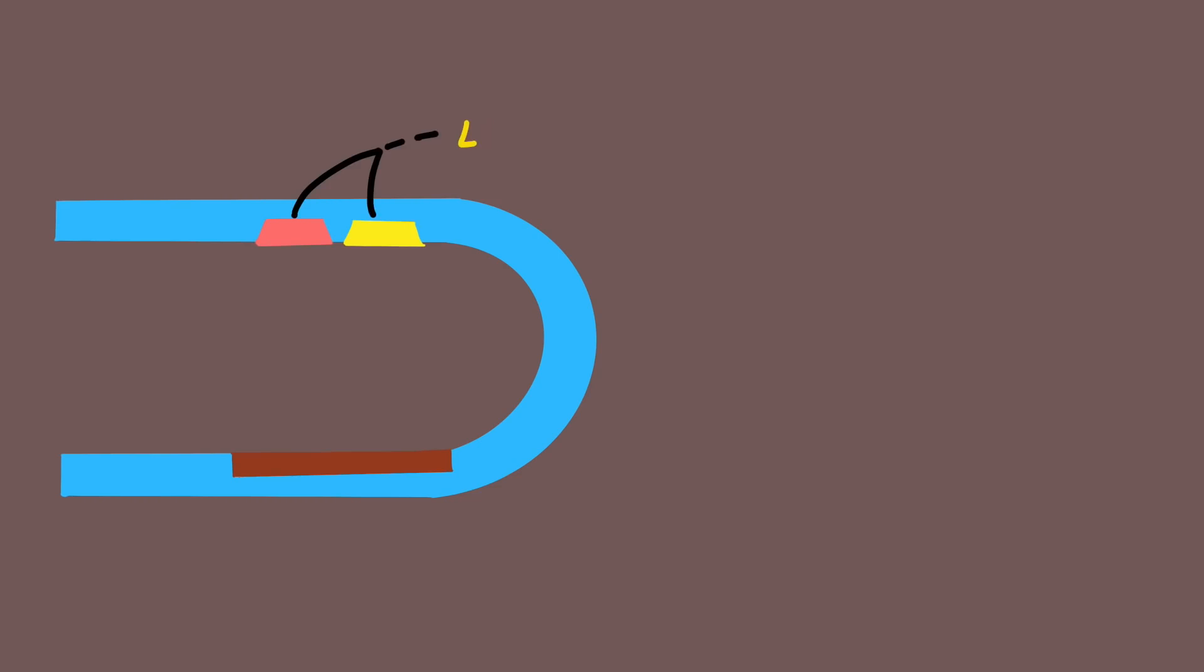Now let's see how pulse oximeter works. Here I have drawn a simple picture. Pulse oximeter uses light to work out the oxygen saturation. Light is emitted from the light source which goes across the pulse oximeter probe and reaches the light detector. Here you can see this is the light source and here is the light detector.